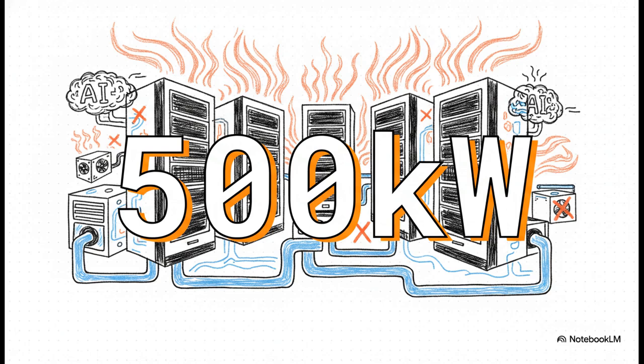500 - that's the magic number you need to keep in mind today. Modern AI and high-performance computing racks are pushing the limits of physics, demanding cooling capacities of up to 500 kilowatts per rack. Just think about that - that is a massive amount of heat. If you try to shove a 500 kilowatt AI cluster into a traditional air-cooled data center, the existing air conditioning infrastructure is going to be completely overwhelmed. The servers would throttle, or worse, just shut down entirely. Honestly, this massive heat density is the main barrier to entry for the AI revolution.